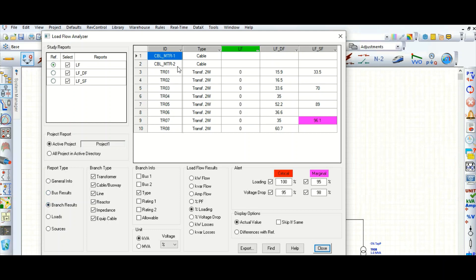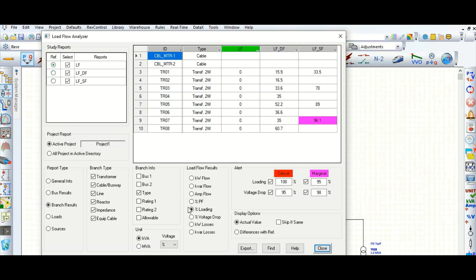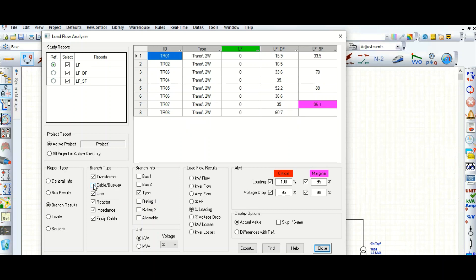Here are the branch results. Branch results cover cables and transformers. For transformer loading, during dual feed configuration, transformer TR-01 loading is 15.9 percent, while in single feed configuration it is 33.5 percent — this unit is percentage. If you don't want to see any element, you can uncheck it, so only the transformer is shown. In this way you can tabulate transformer loading or cable loading.